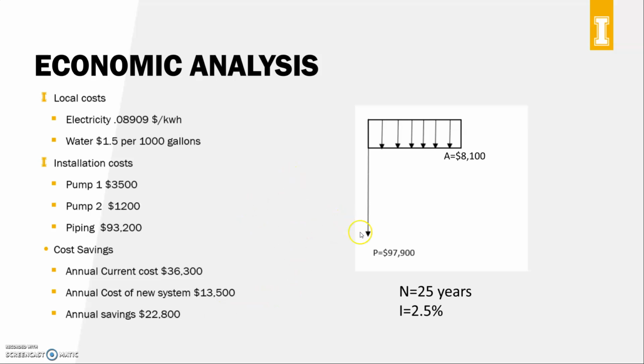Now, to go a little bit more in depth into our economic analysis, I'll explain how we arrived at those numbers. So our P, which is our present cost, is our cost of our piping system as well as the cost of our 2 pumps in order to install them. And that comes out to around $97,000, close to $98,000. And we're operating over a course of 25 years and at an interest rate of 2.5%.